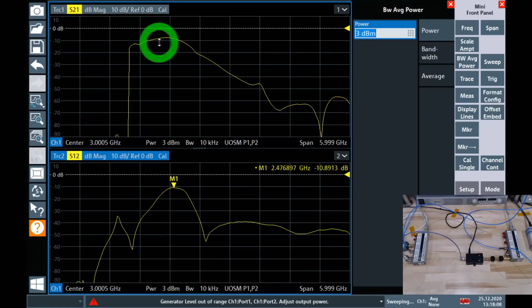Now, most of the time, it's not an issue because this instrument has such a huge dynamic range that for measuring passives, even when they have a lot of loss, you would not run into a problem. That's one of the strengths of this instrument, this huge dynamic range. But now you can see that indeed the PA is turned on almost for the entire ISM frequency band, actually providing quite a bit of gain now, about 13 or 14 dB of gain on the transmit side. So that all makes sense. Let's go back to 0 dB. If I go to 0 dB, this error will go away.